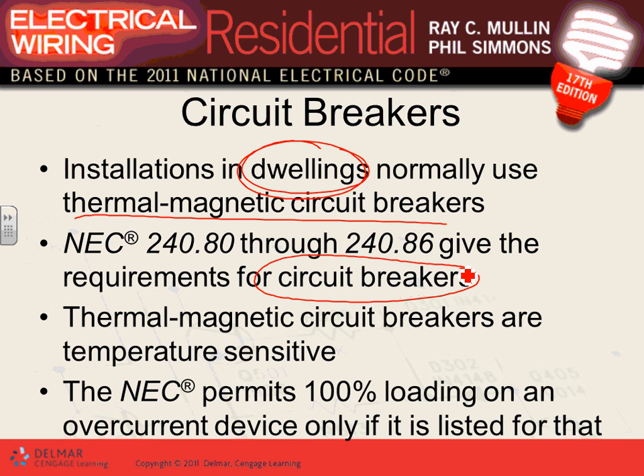Because circuit breakers have a thermal component, they are temperature-sensitive. If you put a circuit breaker in an area that's really hot — say 105 degrees — expect the circuit breaker to malfunction. They'll give you nuisance tripping if the temperature is higher than normal, not because you're pulling more current, but because they're too sensitive to heat.